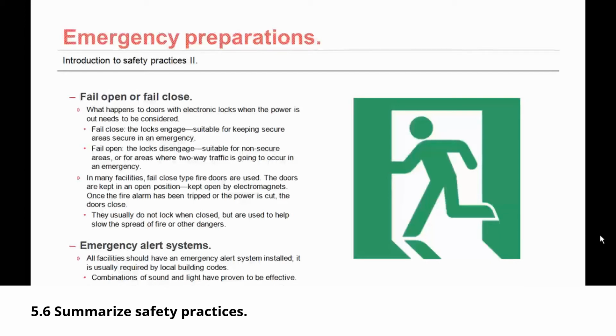In many facilities, fail close type fire doors are used. Usually they're kept open by electromagnetics. Once the fire alarm has been tripped, the power is cut to the magnets and the doors swing closed. They usually do not lock when closed, but are used to help slow the spread of fire or other dangers.